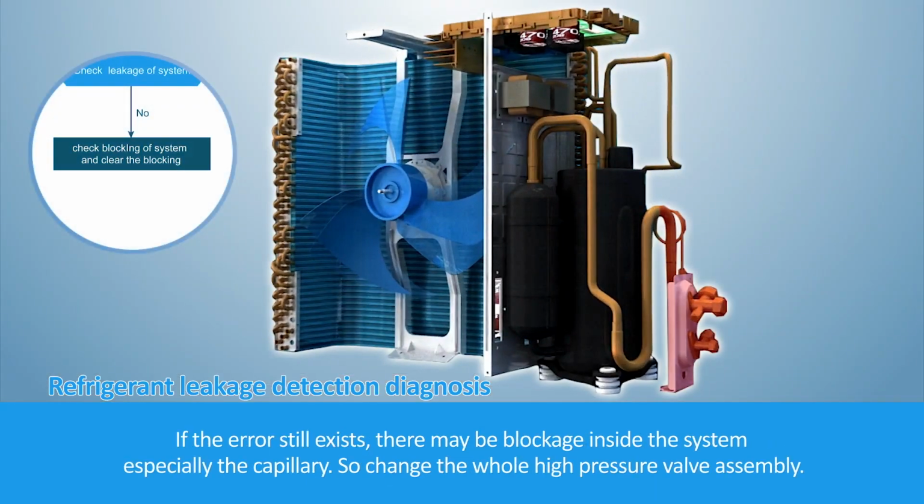If the error still exists, there may be blockage inside the system, especially the capillary. So change the whole high-pressure valve assembly.